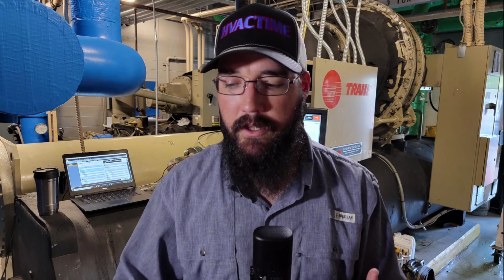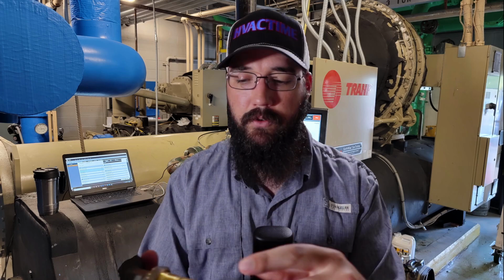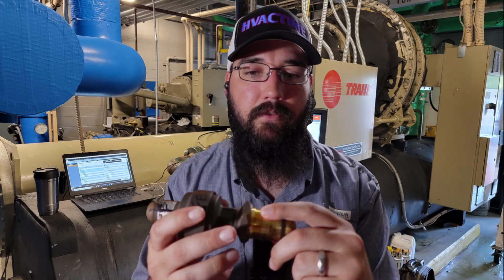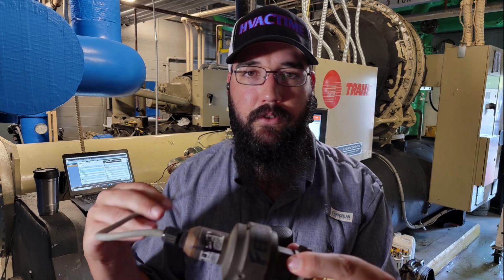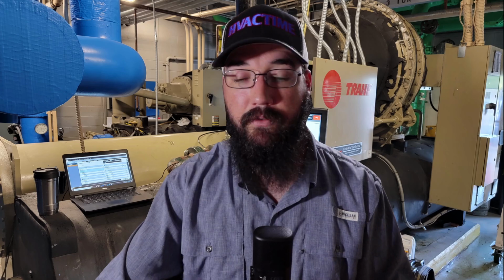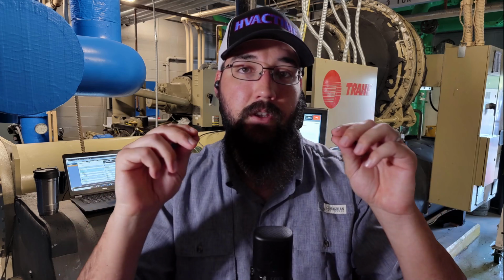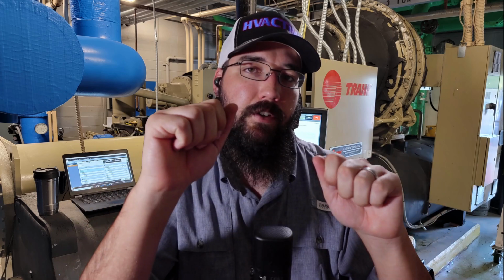5 wires are not going to have anything to ground either, so nothing should be grounded. And you can do that just by testing to the valve body itself. So by just reading from your leads to the copper line set to the valve body, whatever you've got close to you, or if you're doing this from the control cabinet and you're testing at the end of the harness, then just test that to a ground point inside of the cabinet. That works just fine too.